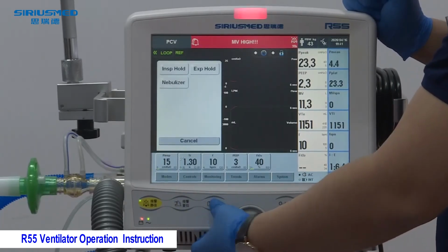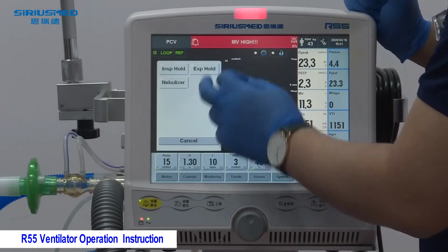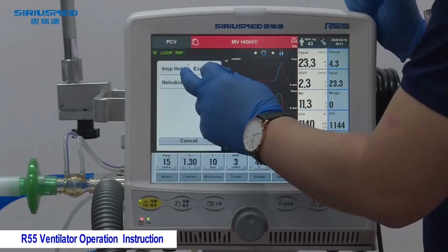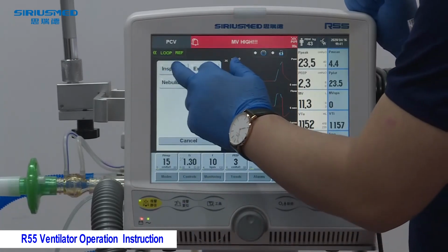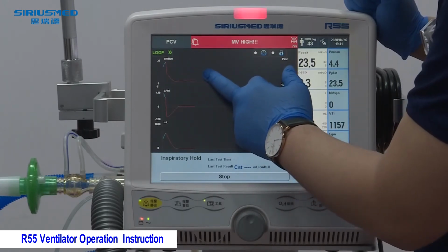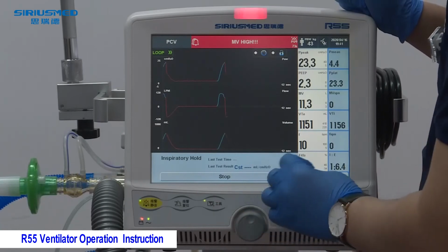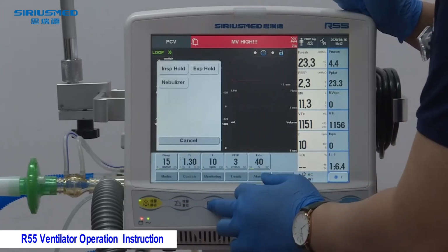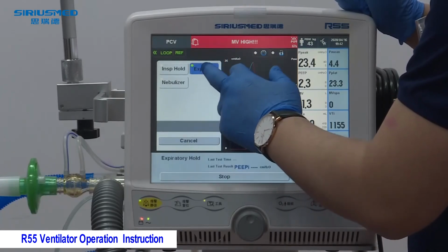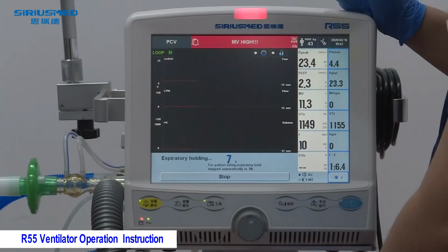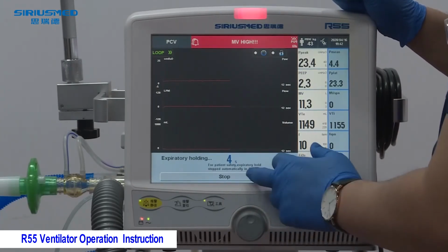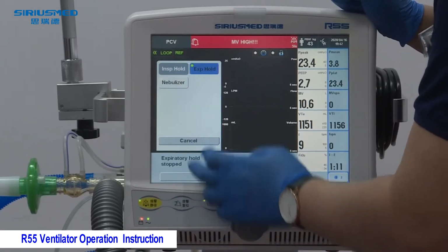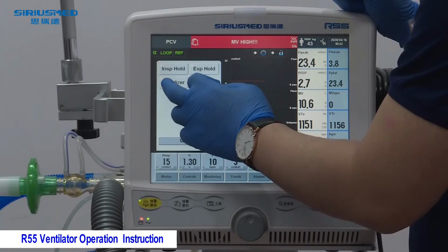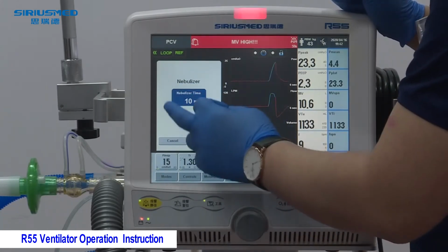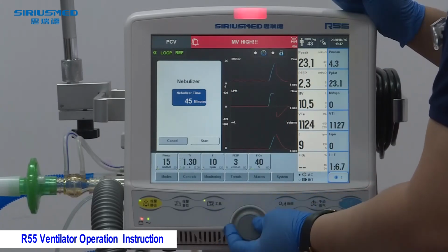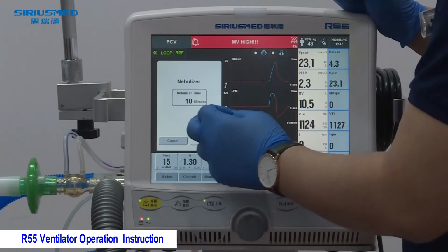And in the tools, there are the inspiration hold, expiration hold, and nebulizer. The inspiration hold means when we touch this one, the machine will keep doing the inspiration without expiration. And the expiration hold is similar. The machine will keep doing the expiration without inspiration. Maximum also 10 seconds. And the nebulizer is to start the nebulizer function. You can also change the time of the nebulizer by the knob. Don't forget to confirm and then start.